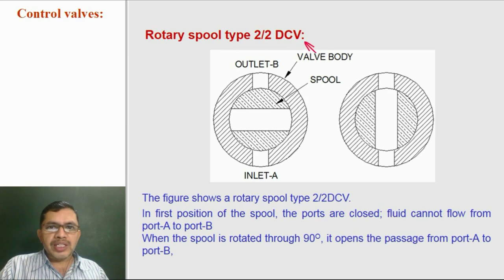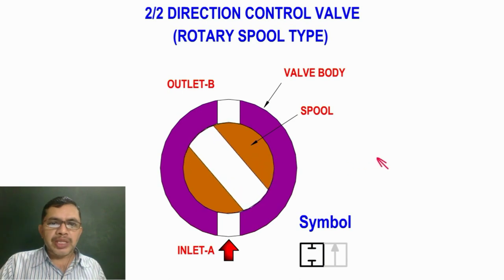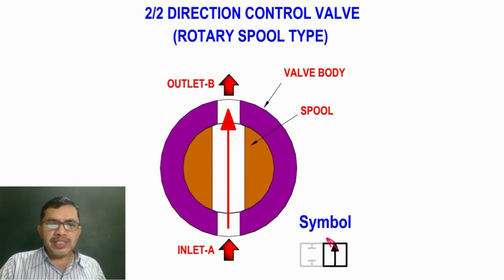Rotary Spool Type 2/2 Direction Control Valve has a spool inside the valve body. In this position, there is no connection from inlet to outlet. When we rotate the spool through 90 degrees, the connection is made from inlet to outlet. In the closed position, both ports A and B are closed — the symbolic representation shows A is closed and B is closed with no connection. When we rotate the spool through 90 degrees, fluid can flow from A to B, represented by an arrow connecting A and B, showing the flow through the valve.